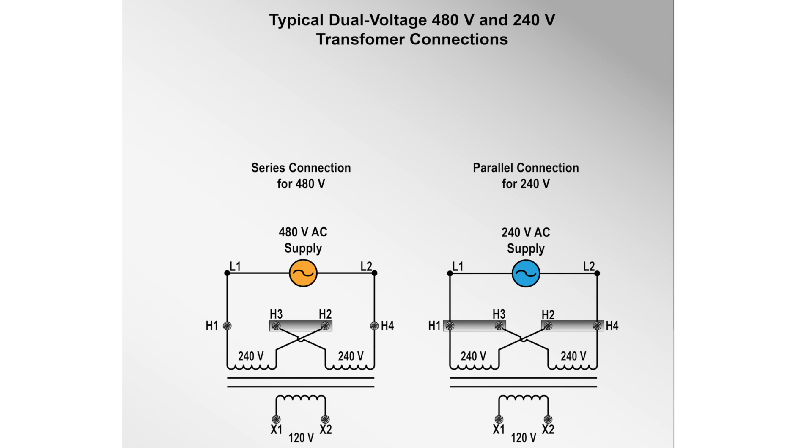If the transformer is used to step down 480 volts down to 120 volts, the primary windings are connected in series by a jumper wire or metal link. If the transformer is used to step down 240 volts down to 120 volts, then the primary windings are connected in parallel with each other.